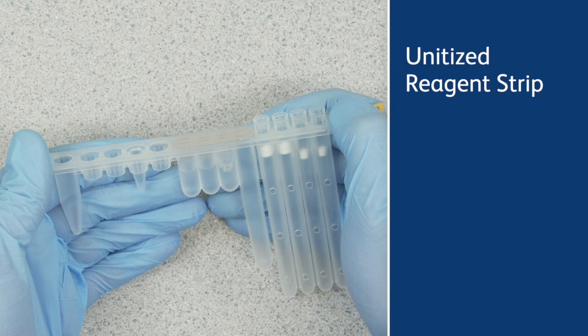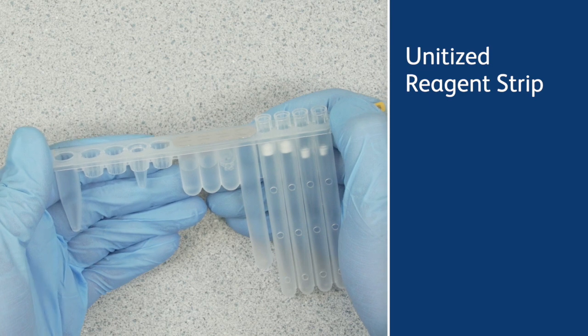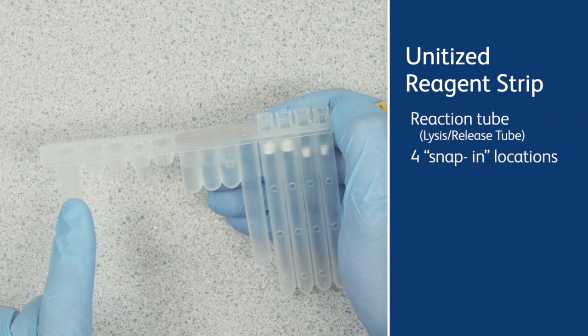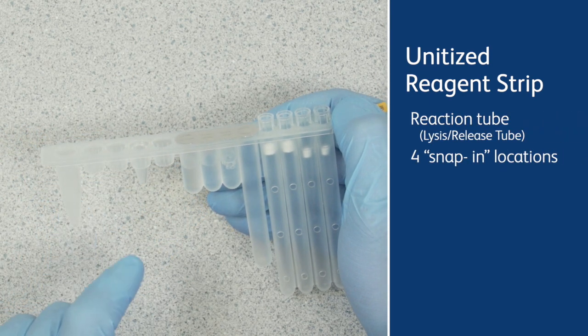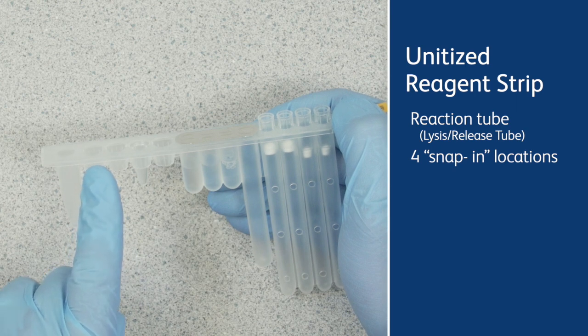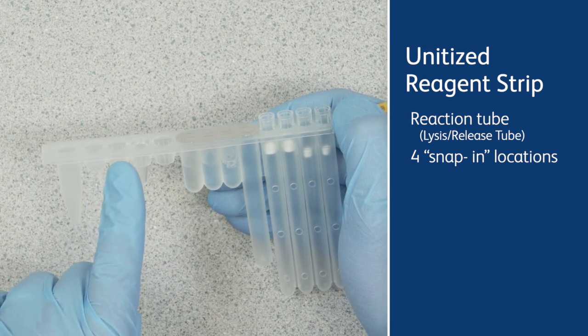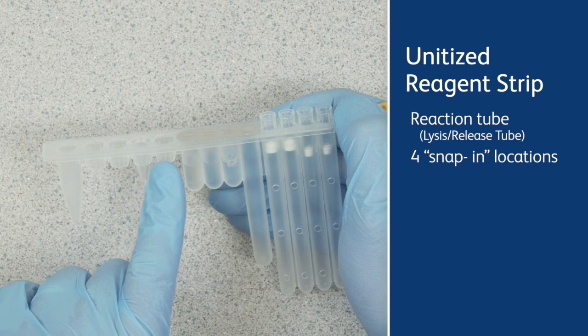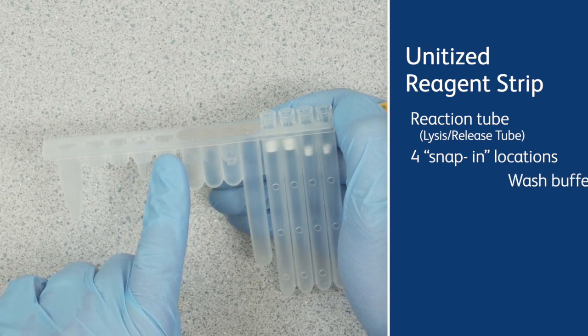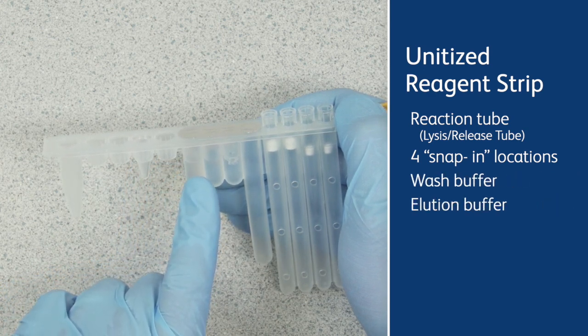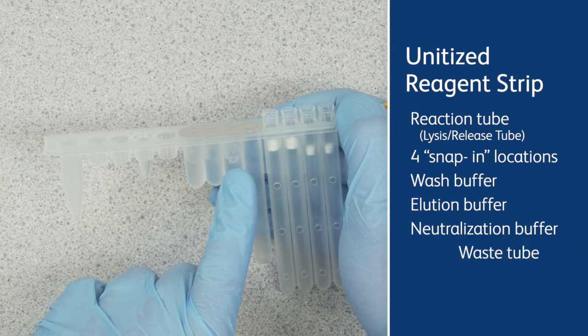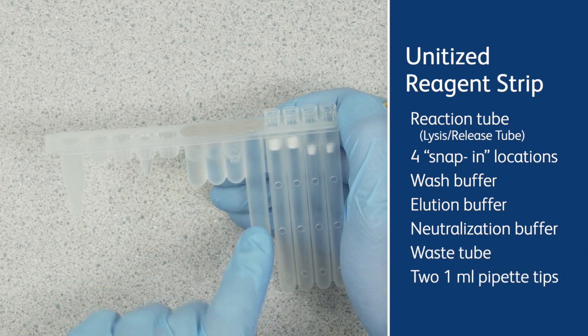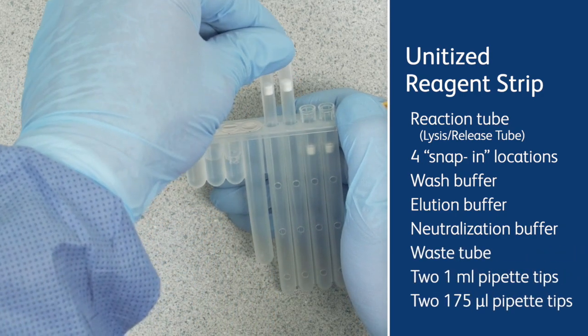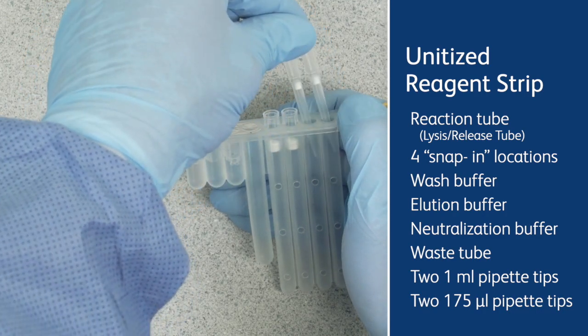The unitized reagent strip includes assay-specific reagents, pipette tips, and vessels for mixing and waste. It consists of the reaction tube and 4 snap-in locations. The snap-in nearest the reaction tube is snap-in 1. Snap-in positions 2, 3, and 4 continue toward the extraction buffers. There is a wash buffer, elution buffer, neutralization buffer, a waste tube, 2 1-milliliter pipette tips, and 2 175 microliter pipette tips.